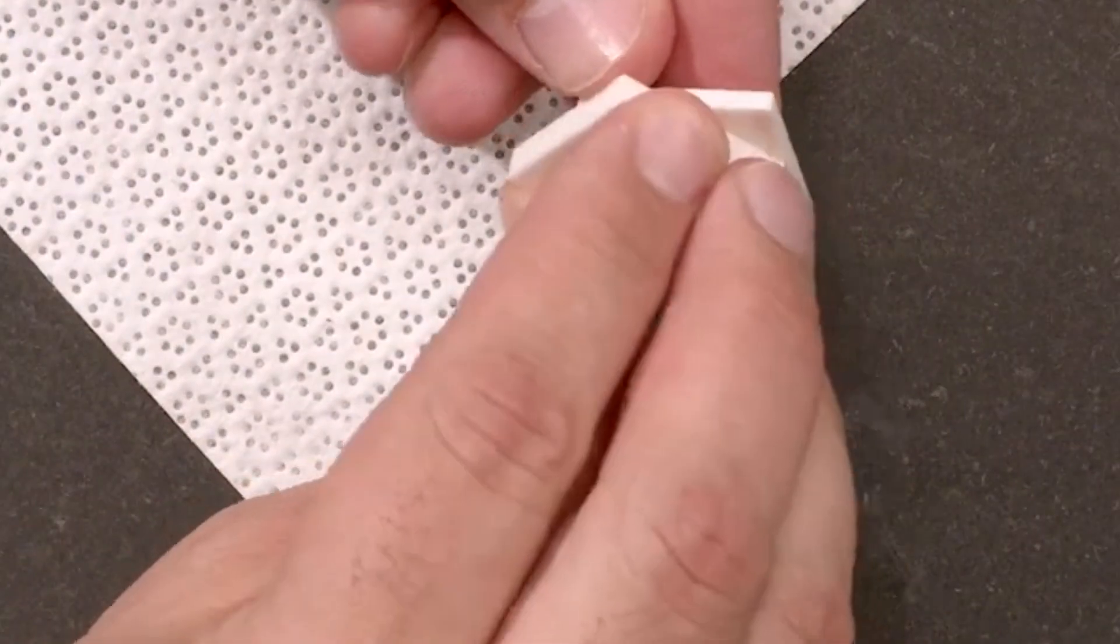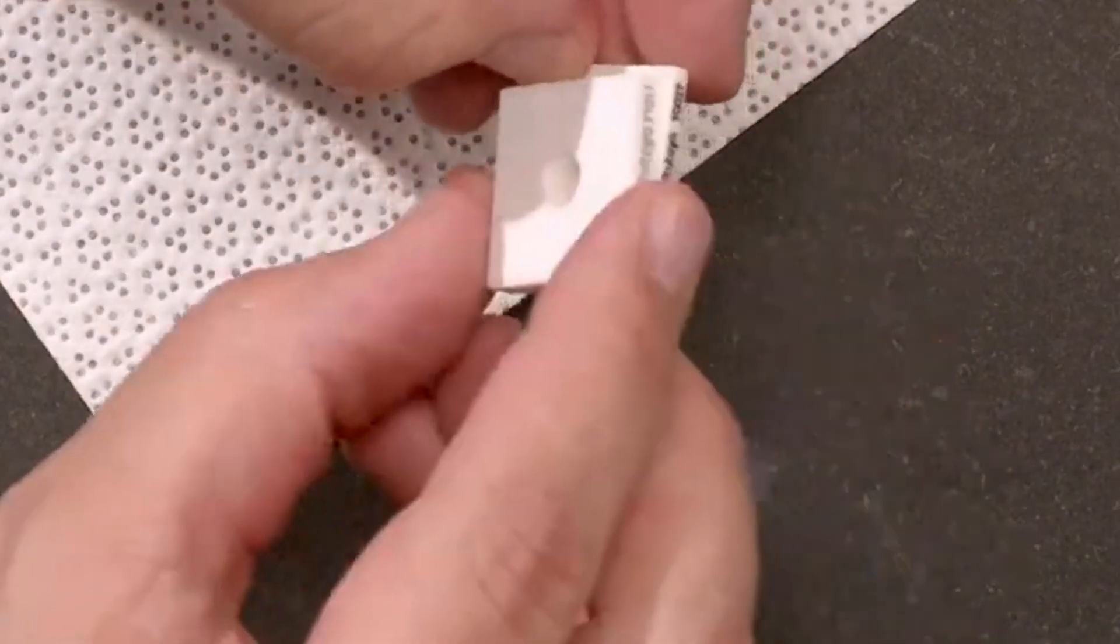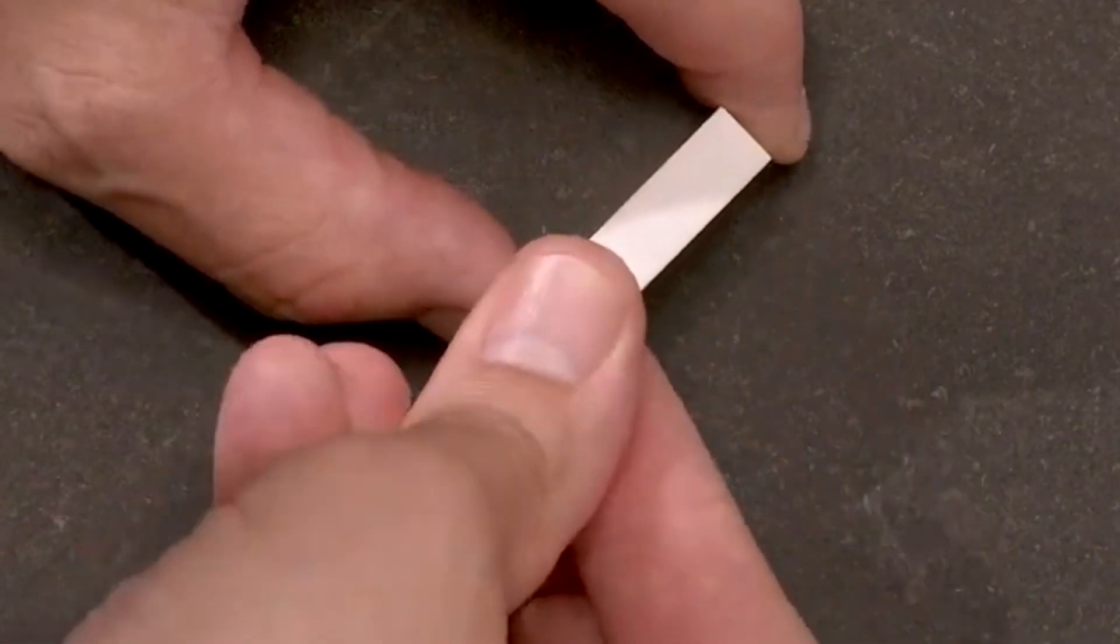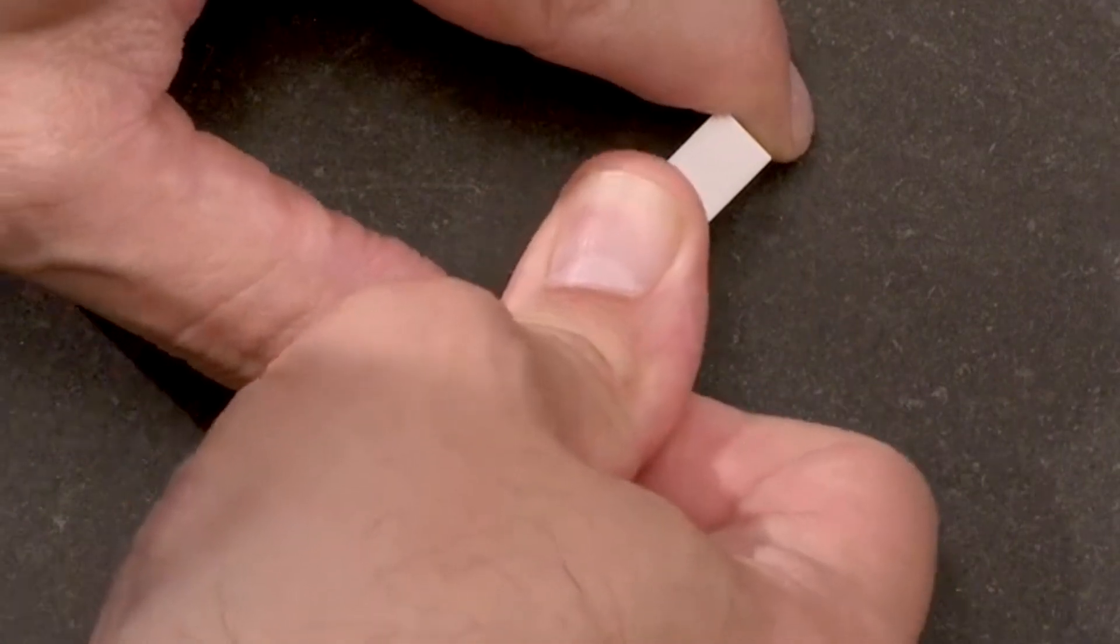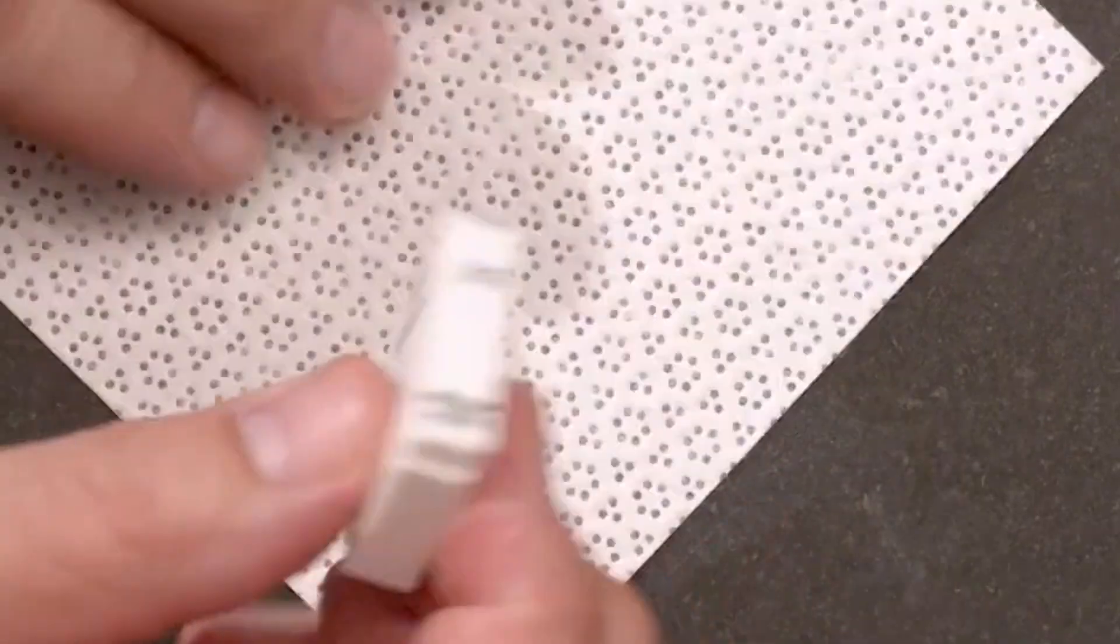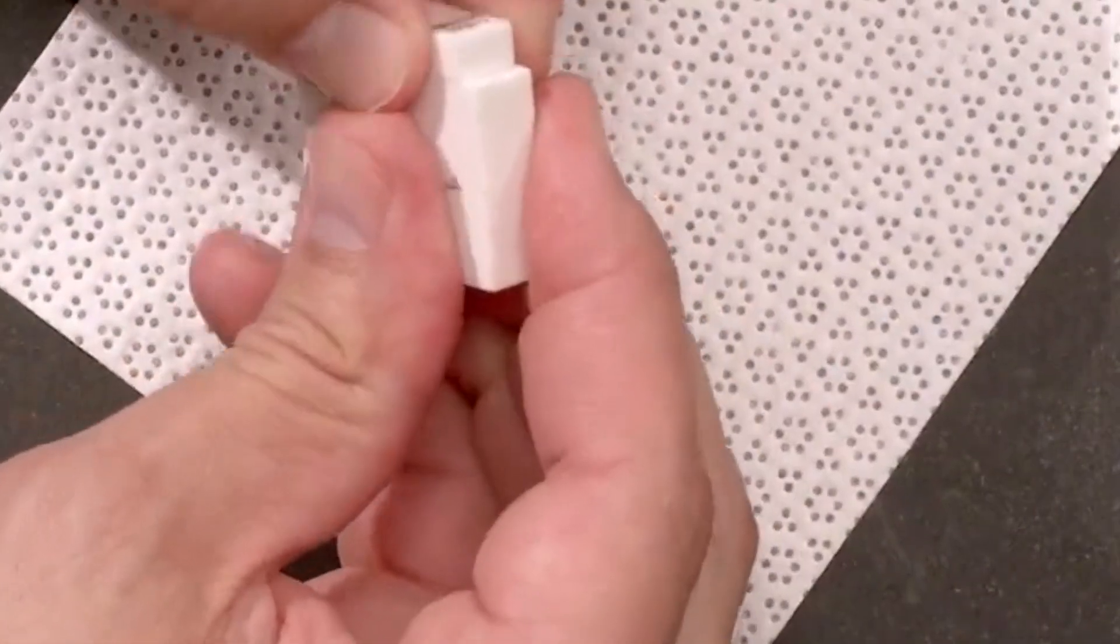On the square blocks, you can typically use a push and twist technique. In fact, it looks like I just accidentally wrung those two together. Alright, so back to these two blocks here. I'm going to push on this while I'm sliding across here. And you can see my thumb turn a little bit white as I do that. And if I did it right, those two blocks are now wrung together pretty well.